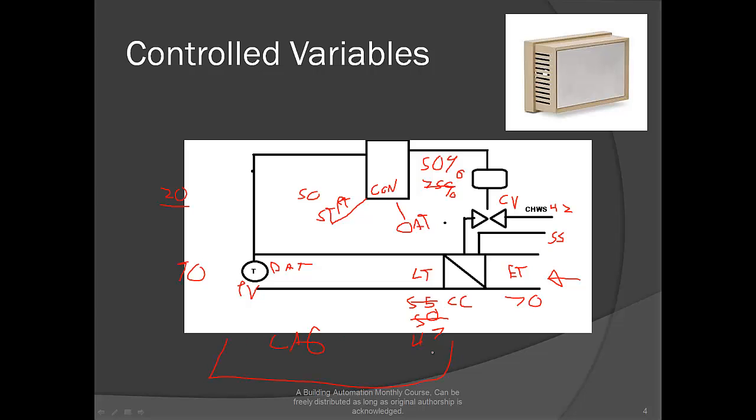What's going on here? I need to give an output to my cooling valve. Temperature drops and eventually temperature is satisfied. But I've cooled down too much. I'm now at 47 degrees. So it's saying you're overshooting. And that, my friends, is called lag. That right there is when your variable starts to change faster than your feedback. So we're dropping the temperature too quick. Controller can't keep up or sensor's too far, one of the two. And because of that, we have to add in some tuning. We'll talk about that with PI, proportional integral control. And we'll talk about how we use that to tune a loop. And just a toss out to one of fellow bloggers out there, Abel Ramirez has a blog on loop tuning that I will put in the comments.